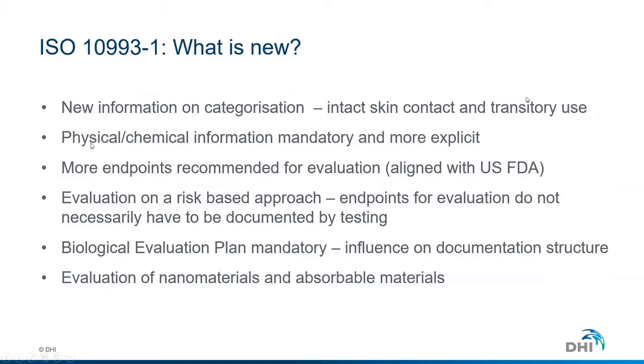So that's quite important as well if you're assessing drug delivery devices, like for instance, injection devices. Then it makes physical and chemical information mandatory, and the requirements are now more explicit. So that puts more requirements and needs for information on you as a manufacturer of a medical device. There are more endpoints recommended for evaluation of the device for biocompatibility, and that is aligned now with the requirements from the US FDA guidelines.